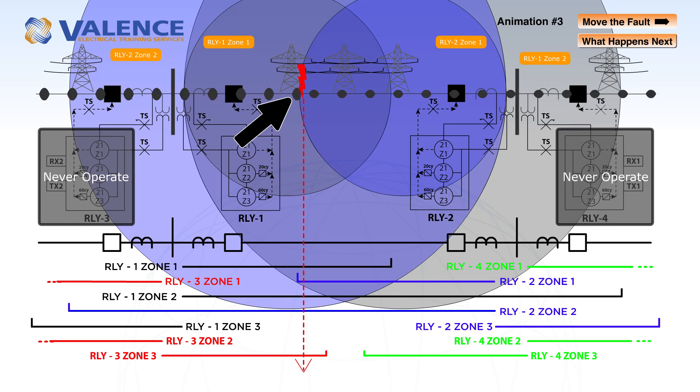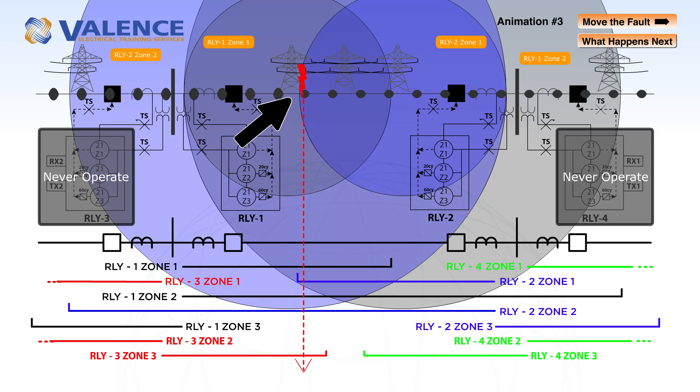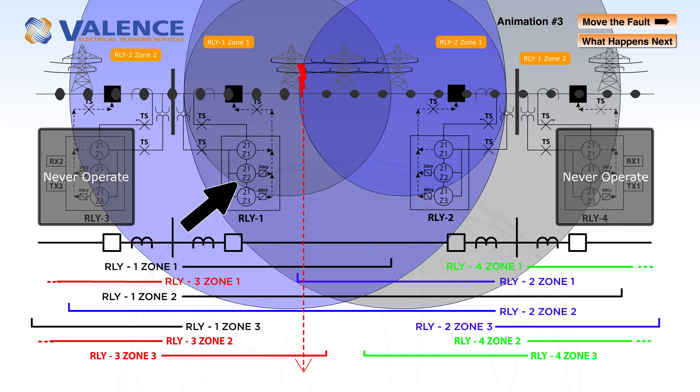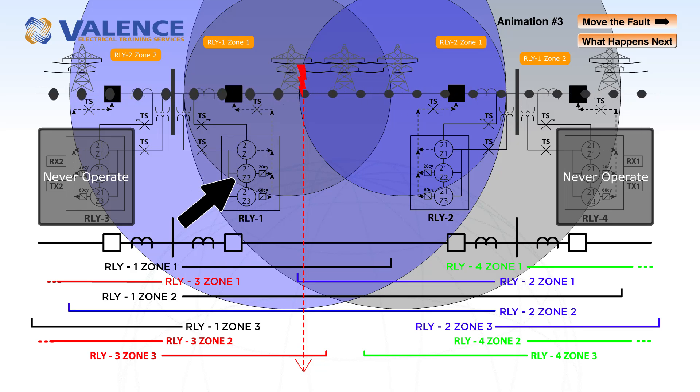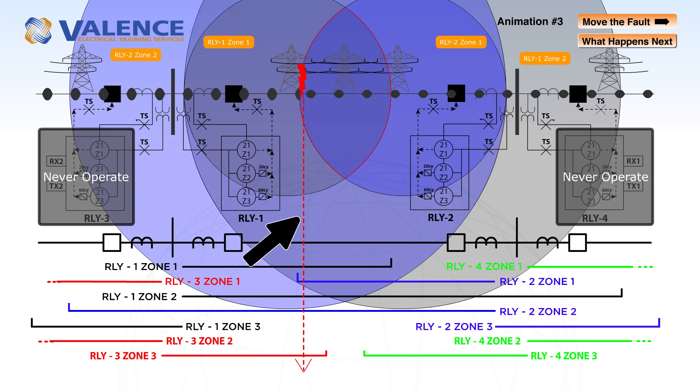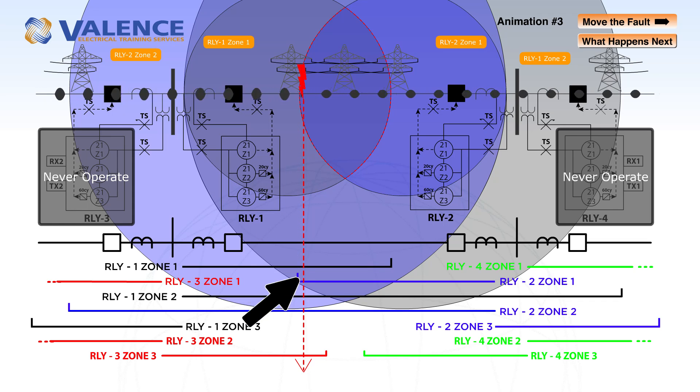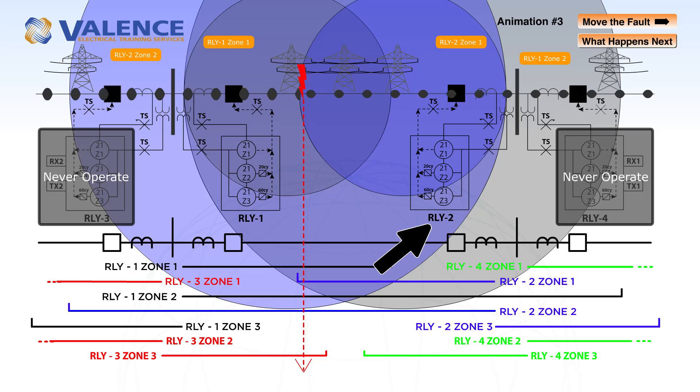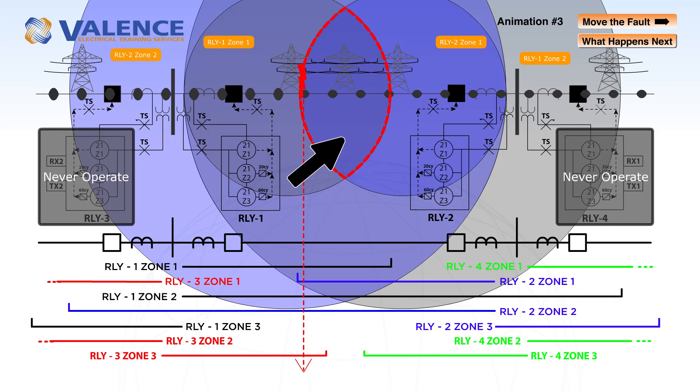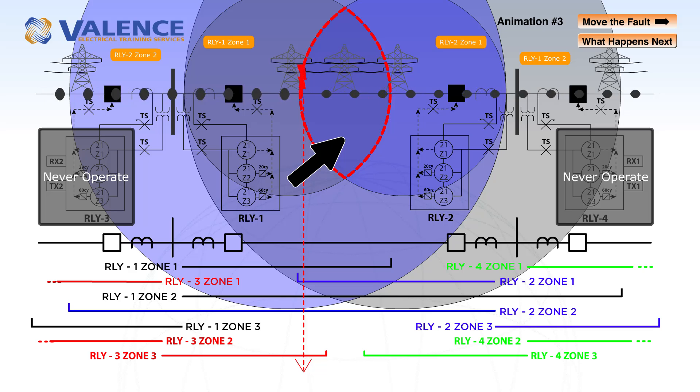When we move the fault to the other side of relay 2 zone 1, relay 1 is still going to detect zone 1 and zone 2 pickups because the fault is inside both of those zones. Relay 2 is going to detect the same thing because we're in the overlapping region between the two relays zone 1.